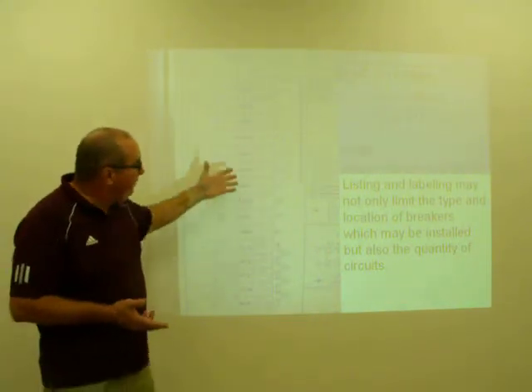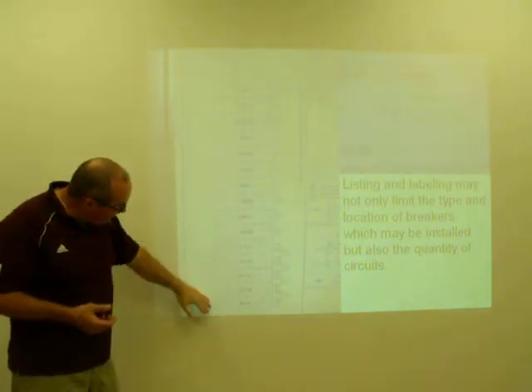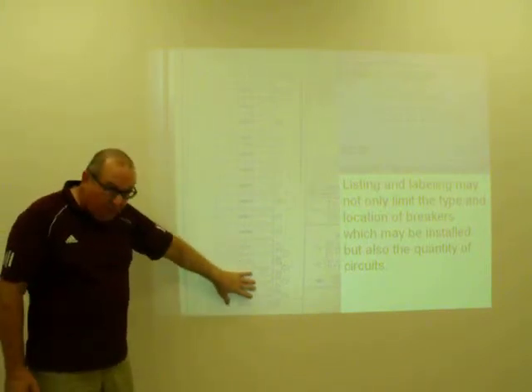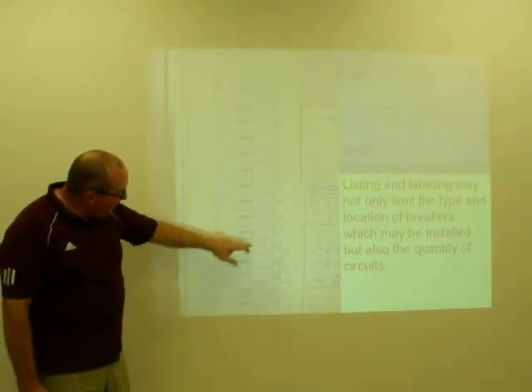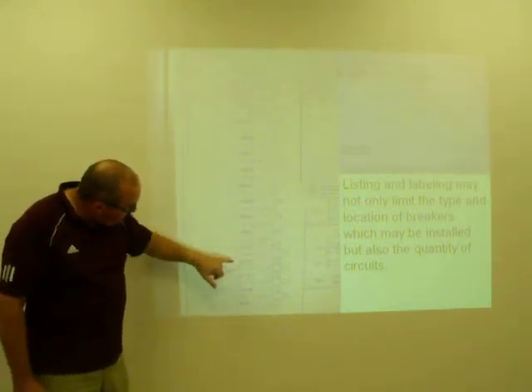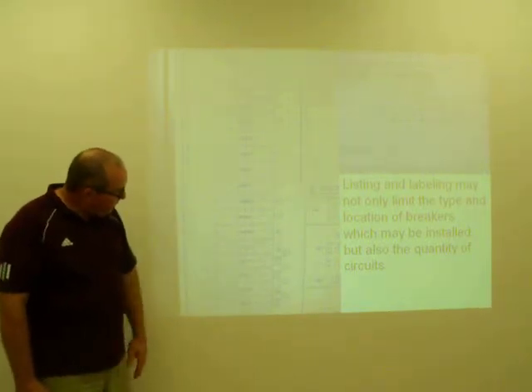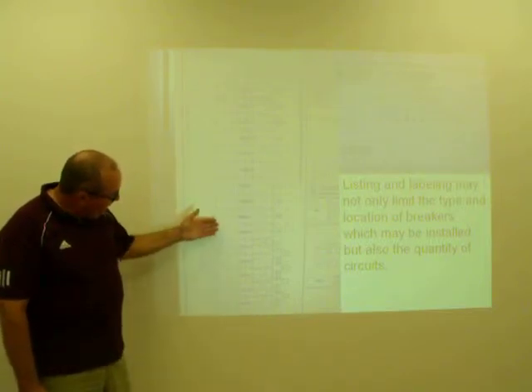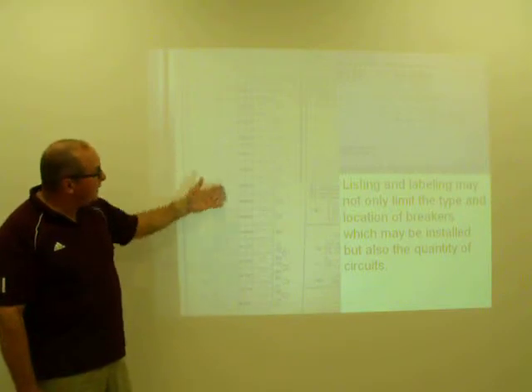brand. And again, this is another example of how you can have a panel board that is 40 circuits if you use twin breakers or tandem breakers in these slots. So you can have 30, 31, 32, 33, 34, 35, 36, 37, 38, 39, 40 total breakers in this panel. Or you may only be able to have a fewer number depending on the construction.